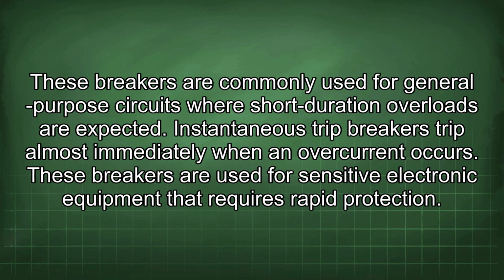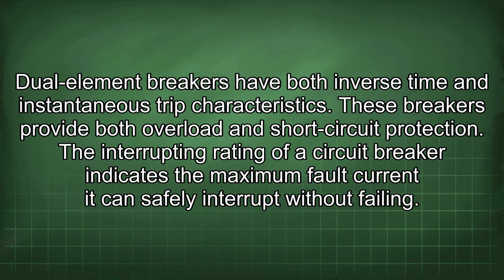Instantaneous trip breakers trip almost immediately when an overcurrent occurs. These breakers are used for sensitive electronic equipment that requires rapid protection. Dual-element breakers have both inverse time and instantaneous trip characteristics. These breakers provide both overload and short-circuit protection.